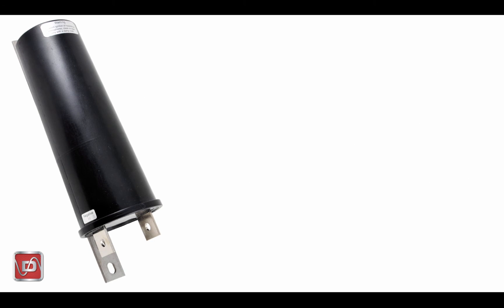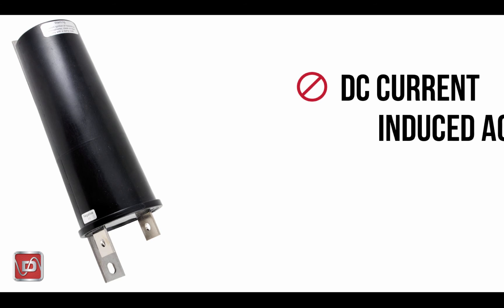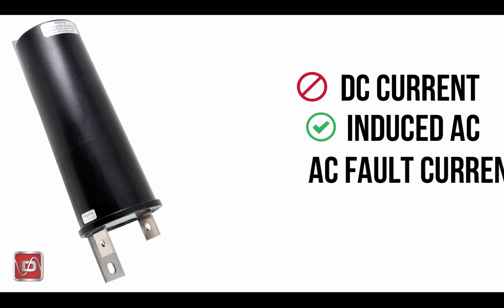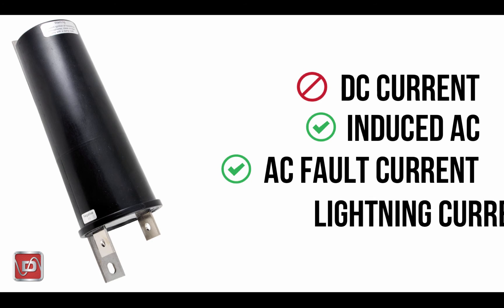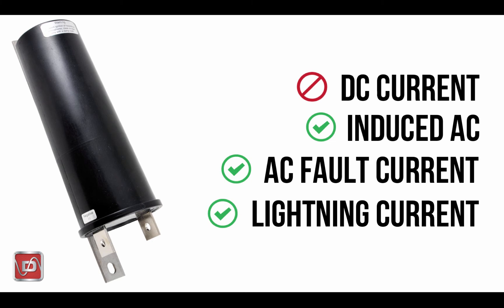It might help to think of this as a filter. Decouplers isolate or block the conduction of DC current, which is desirable in optimizing your cathodic protection system. This prevents the loss of CP current to grounding system materials or other metallic structures. At the same time, decouplers such as the SSD conduct induced AC current, which is desirable for AC mitigation applications. So it filters or blocks DC, but it lets AC flow right through.